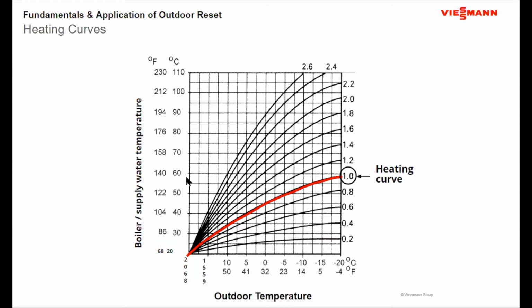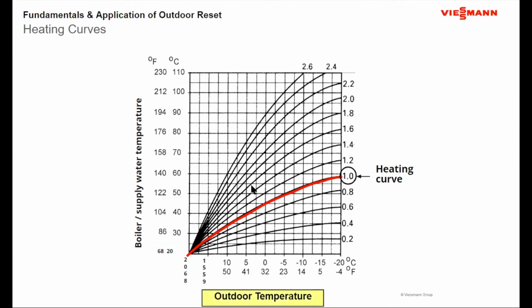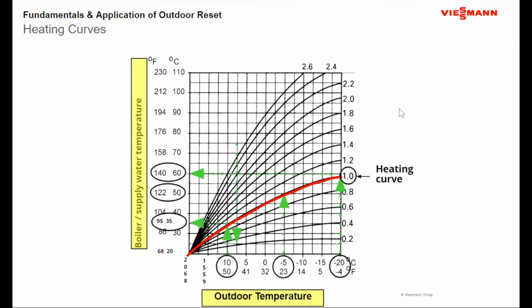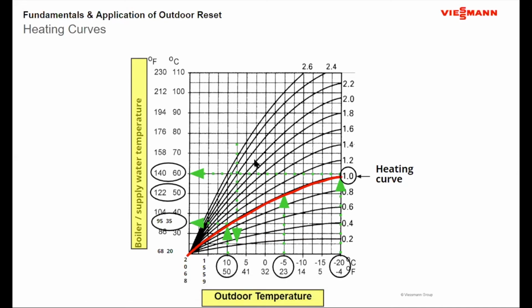So for instance, if I had a design day of -4 degrees Fahrenheit and my design water temperature was in the neighborhood of about 135 degrees, my heating curve would be about a 1.0. So on the design day, I'd be at about 135-degree water temperature. On a 32-degree day, I'd be somewhere in the neighborhood of maybe about 110-degree water temperature. But again, that heating curve becomes a combination in the relationship between outdoor temperature and water supply. So for instance, a -4-degree day, if they moved it up a little bit, it's 140. A 23-degree day, 122. A 50-degree day, 95-degree water temperature. And the thing is, if this is the right heating curve, on these days with those water temperatures, the building's going to stay at a constant 70 degrees or 68 degrees Fahrenheit. And that's really our goal when we start to do outdoor reset control.